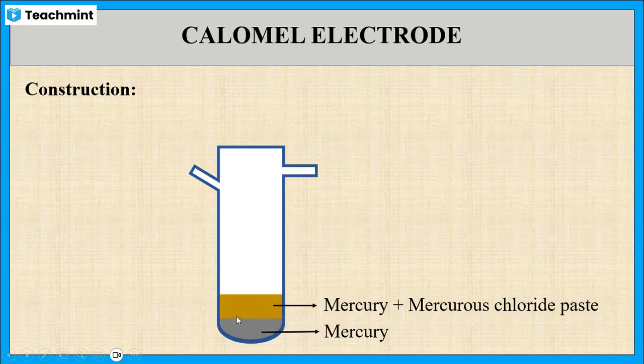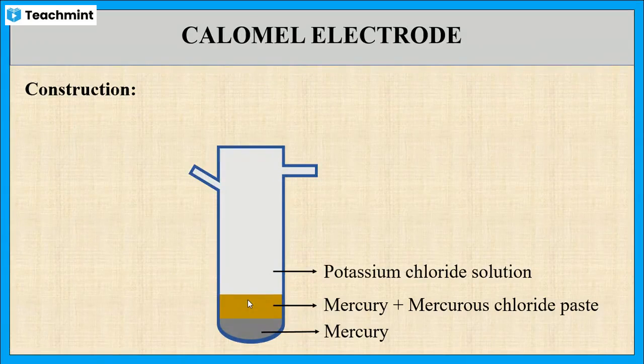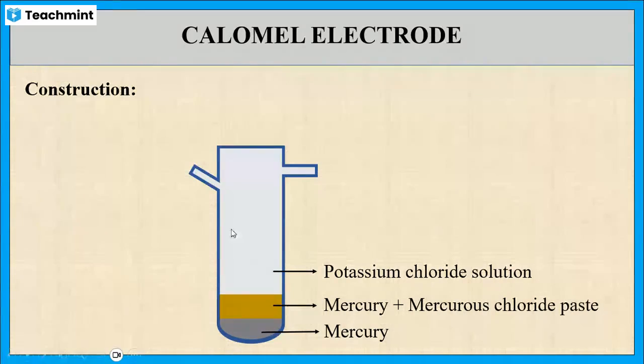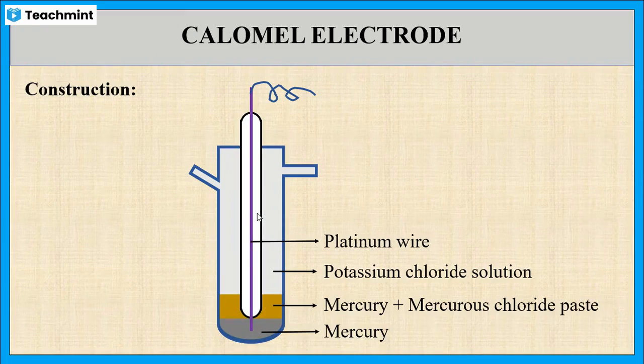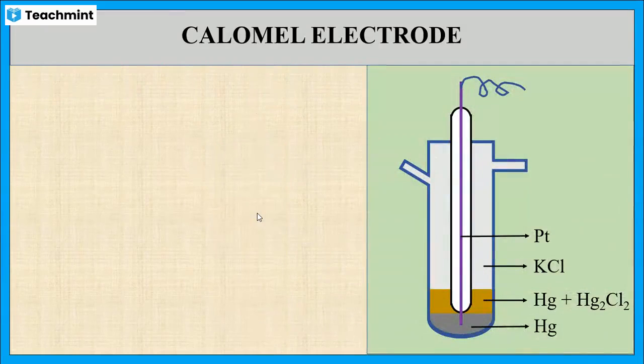Now let us see the construction of the calomel electrode. This calomel electrode mainly consists of a glass tube in which mercury is placed at the bottom. Above the mercury level, a paste of mercury and mercury chloride is placed, and the remaining space is filled with potassium chloride solution. So this glass tube contains mainly three layers: the first layer is mercury, the second layer is mercury and mercurous chloride paste, and the third layer is potassium chloride solution. A platinum wire is dipped into the mercury, which is used to connect to the external circuit.